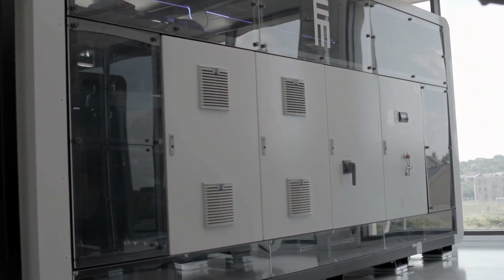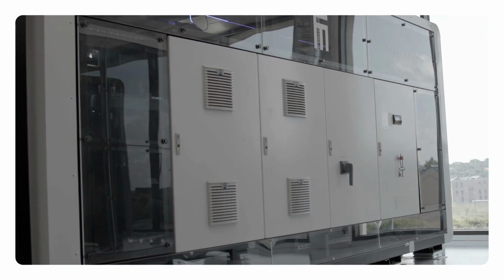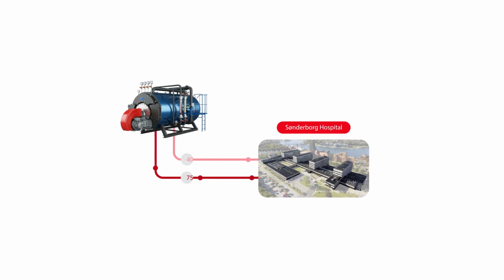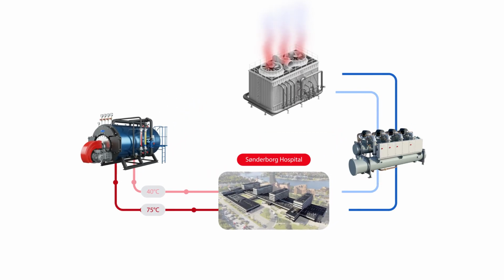Let's take a closer look at how the hospital treated heating and cooling separately, and how adopting an integrated system changed that mindset. The hospital used gas boilers for facility heating and domestic hot water at 75 degrees Celsius, an energy-intensive, carbon-heavy, standalone system. The hospital's chilled water system cooled the building and medical scanners, but the heat removed in this process was simply rejected to the atmosphere through the cooling towers, wasting significant usable energy.